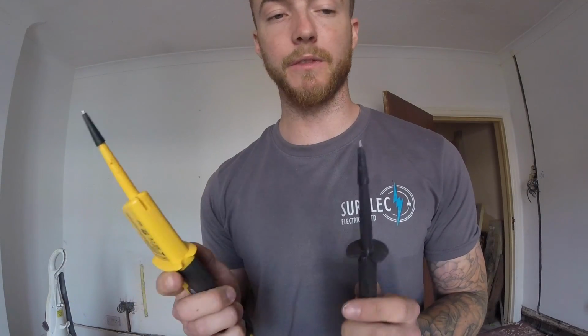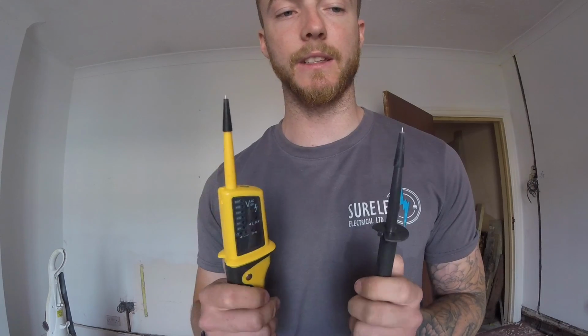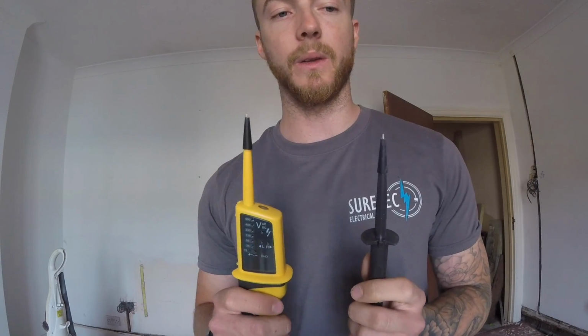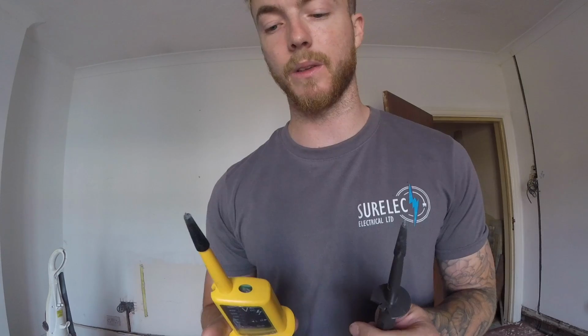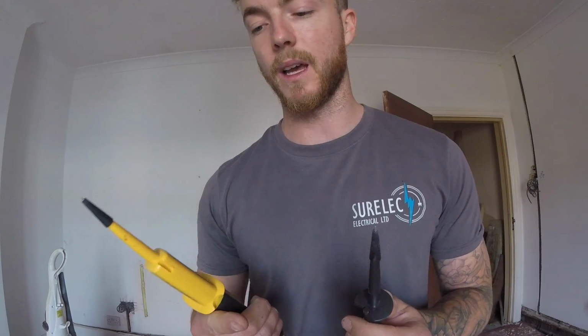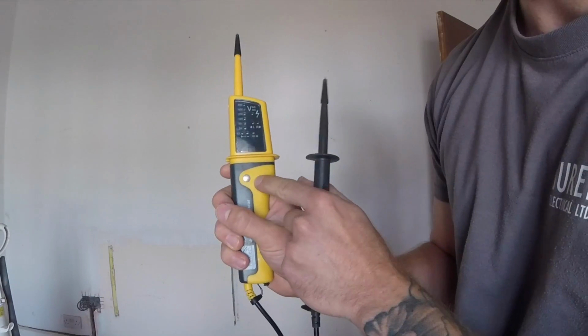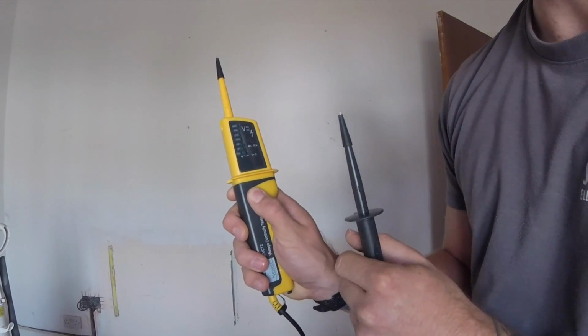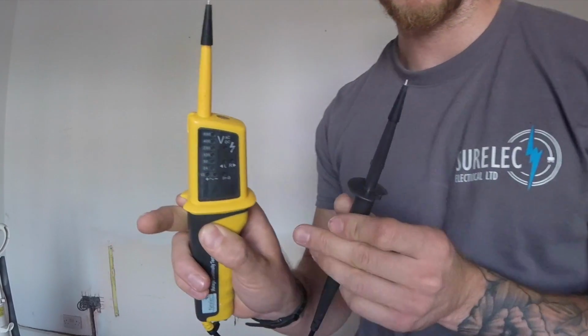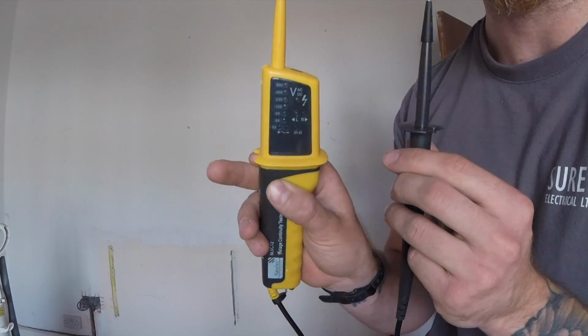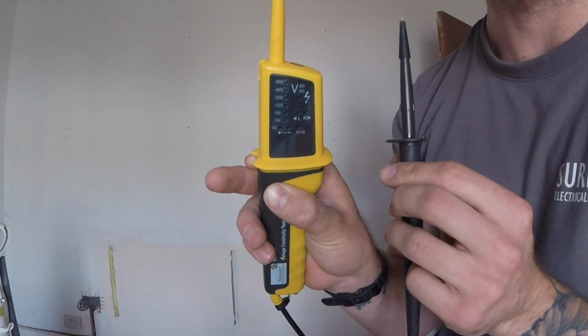So last but not least, I've got my voltage continuity tester here. This is ideal for safe isolation. The reason for using one of these for safe isolation is there are no settings to touch. There's no chance of you having it on the wrong setting, not reading exactly what you should be for proving when something's dead. So all you have to do is hold your thumb on the little metallic button there. Hold that, say put one probe on your live, one probe on your earth for when you're proving something's dead, or the whole phase sequence.